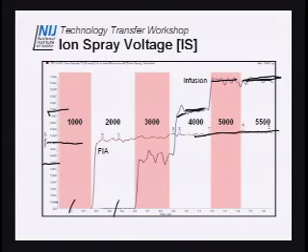So ion spray voltage makes a difference. We set it basically as high as we can set it without having something bad like some sort of discharge going on. One of the nice things about having that bath gas that fills the whole turbo spray chamber is it actually suppresses discharge in there. And they tell us if you're having a problem, look inside. If you see a blue glow, you're having a discharge.